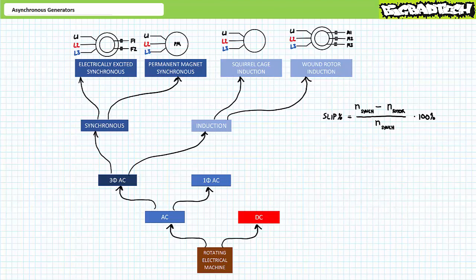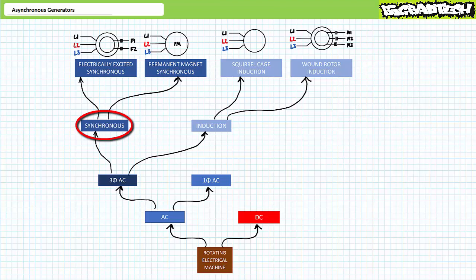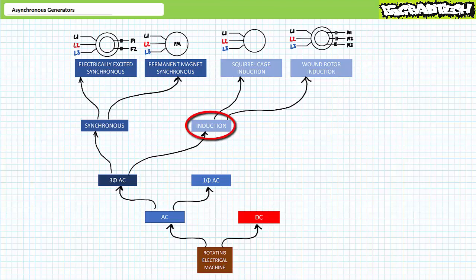Besides the rotor and stator speed relationship, another defining feature of the synchronous versus induction split is a particular generator's ability to stand alone. Synchronous generators are black start capable — meaning from utter darkness, i.e., a grid in a completely depowered state, they can begin generation even if in isolation. A vast majority of large mission-critical generators like hydropower dams and coal-fired power plants are synchronous generators. Asynchronous generators, in contrast, necessitate connection to an existing power grid for them to work at all — it takes power to make power. If the grid is down, an asynchronous generator cannot be used to restart it, barring exotic mechanisms.